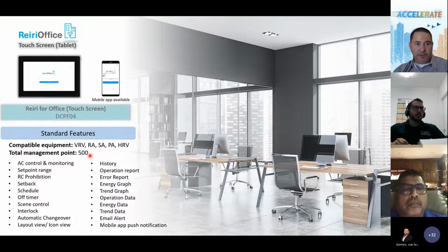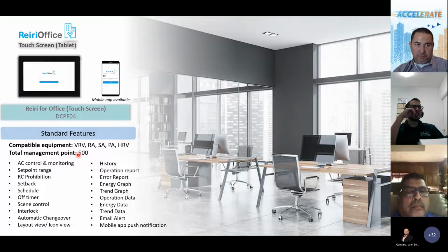On the other side, I'm going to be connecting VRV indoor units to this controller, but each VRV indoor unit counts as one point. It doesn't matter if you're controlling the swing, the fan speed, or the return temperature, it only counts as one. So my maximum is going to be 500, okay? I hope you guys understand that.